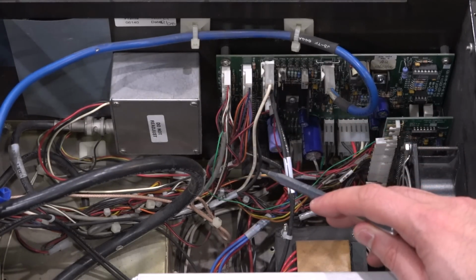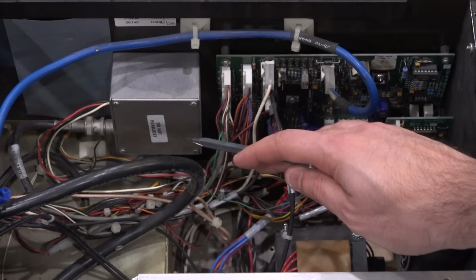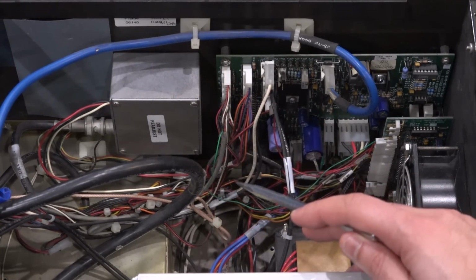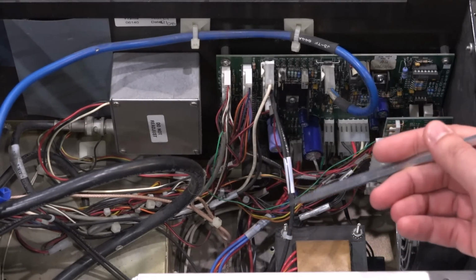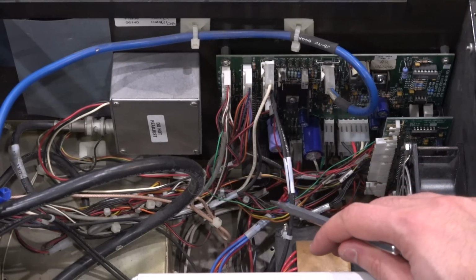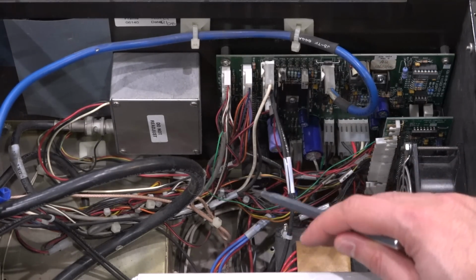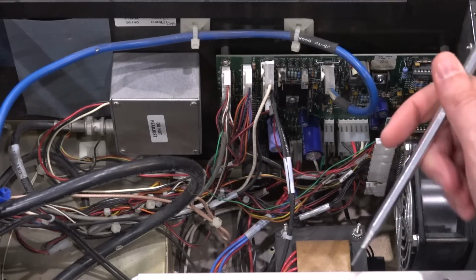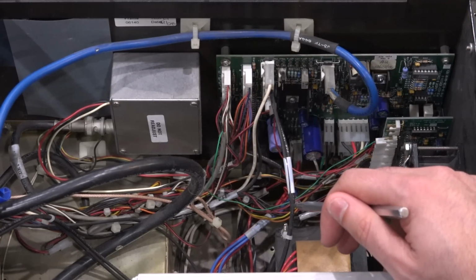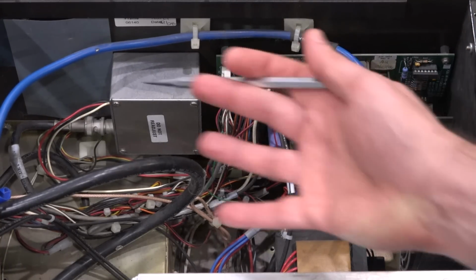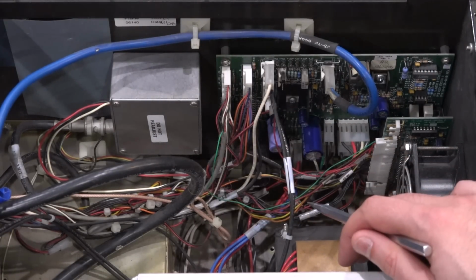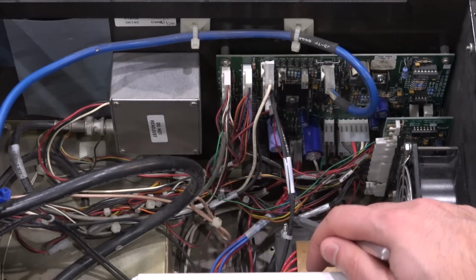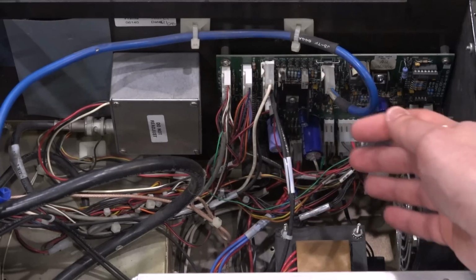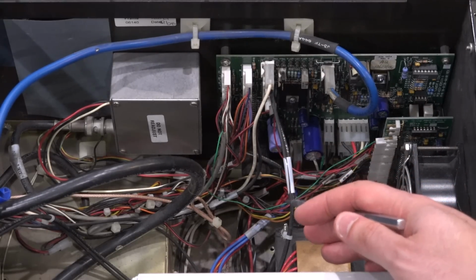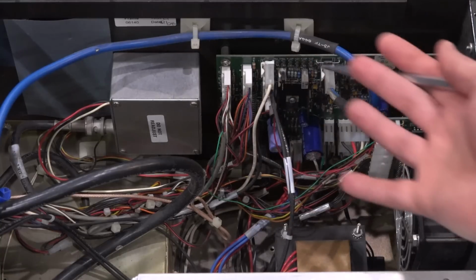There's a few analog interfaces, particularly this one goes into a box that says do not readjust, a high voltage power supply going in. So I'm pretty sure that this does no interpretation at all for the fluorescence information from the X-ray detector. All that signal appears to be sent to the PC card in an analog format, and I think that then performs computation and figures out what's going on. This box is essentially dumb, just as most of the controllers. But because nothing is labeled, I have to be very careful. Removing all of these wires is essentially required to remove that main X-ray unit, because there's really nothing else in here.